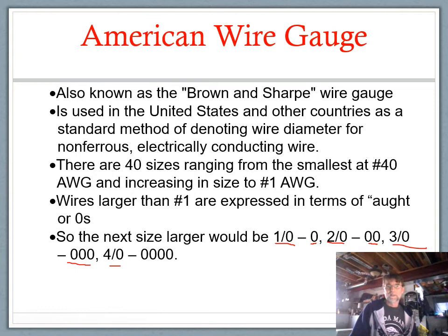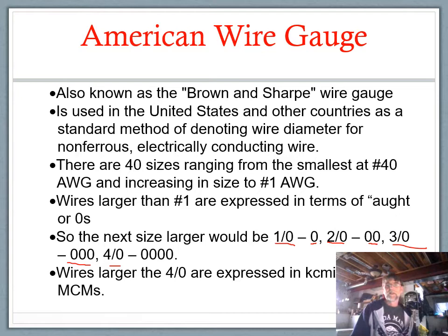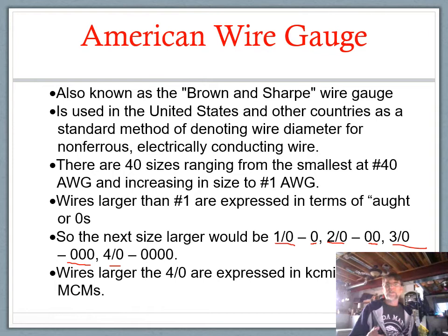Four ought is the size used for a 200-amp service, for example. These aren't standard AWG sizes per se — they're kind of in a category by themselves: one ought, two ought, three ought, and four ought. Once you get to conductors bigger than four ought, we use circular mil area. Beyond four ought, the next size up is 250 kcmil. So beyond four ought, we talk in terms of kcmil or MCM.